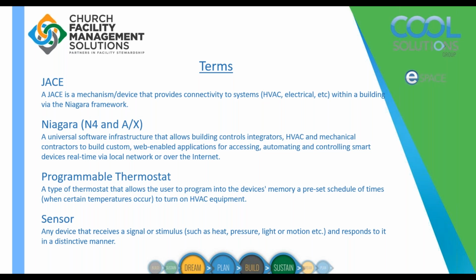What we find is many times an HVAC company will say yes, we can do control systems, and they'll sell a branded control system, but they don't have a certified controller on staff. Everything's great as long as the system doesn't experience issues or you don't try to make customizations. When you start doing that, if they don't have a certified controls person, you're unable to do the things you might need to do, and it's very difficult to get troubleshooting done if they're not certified on that.